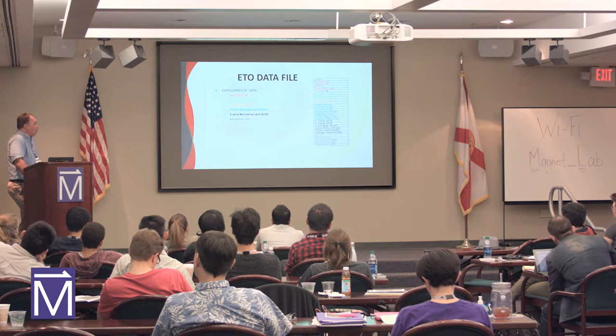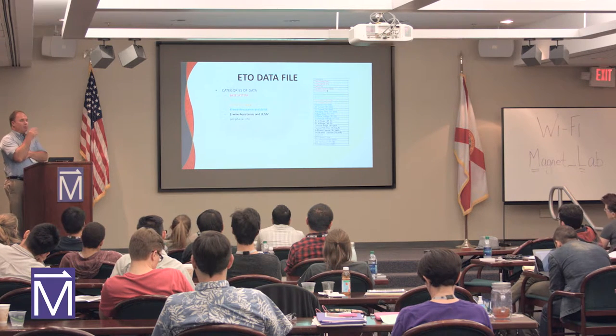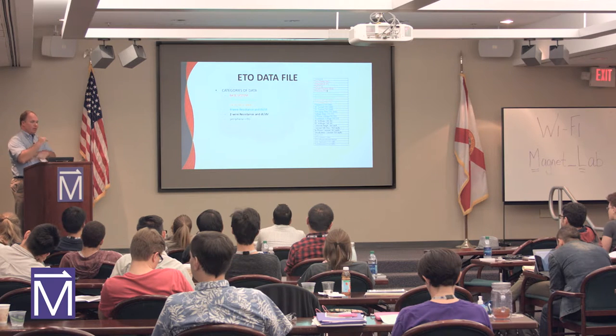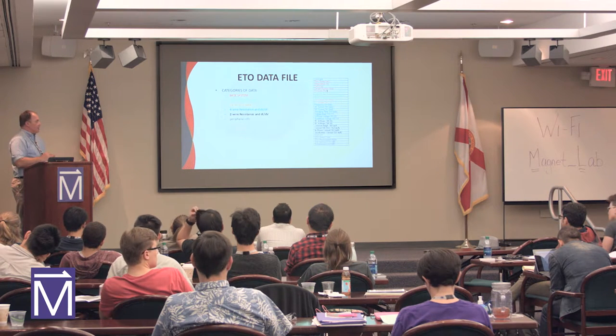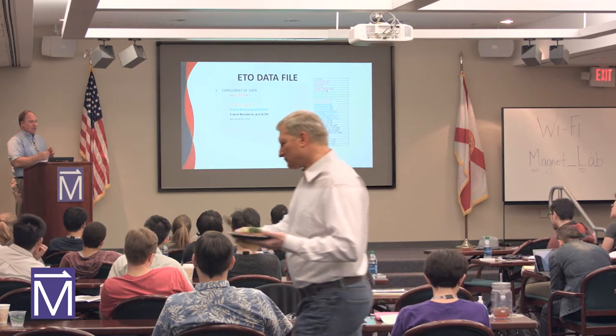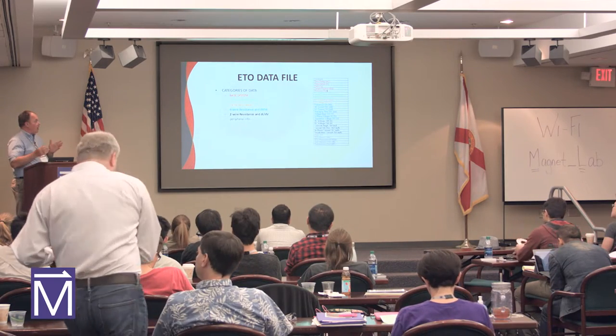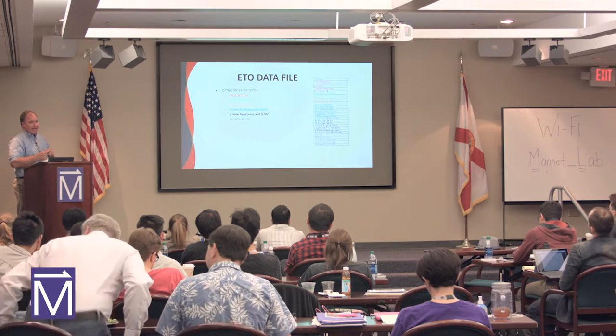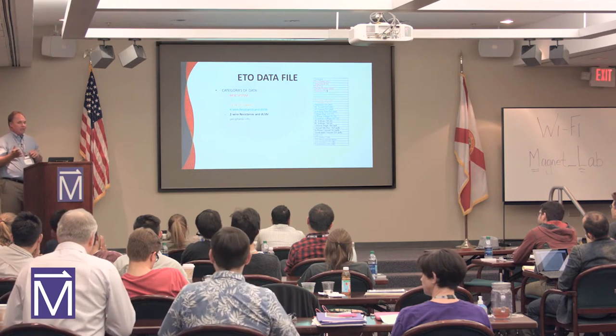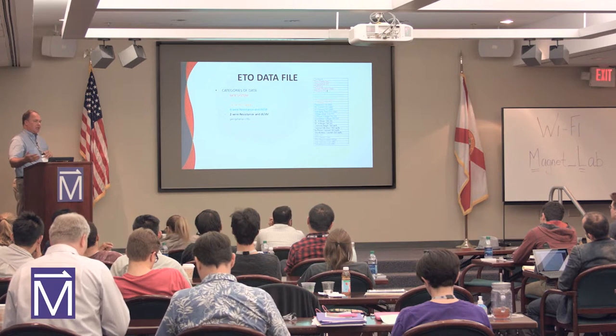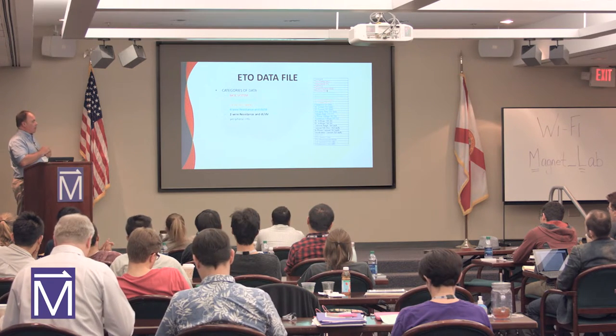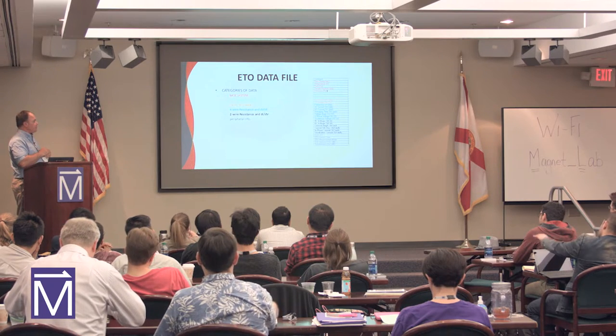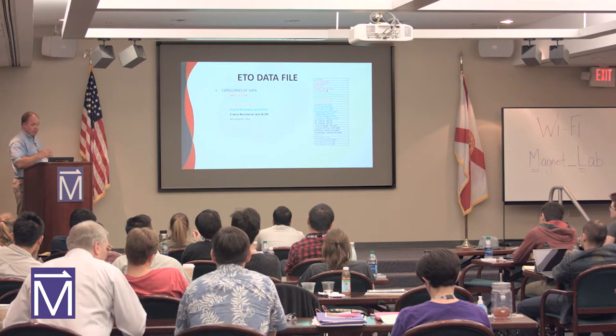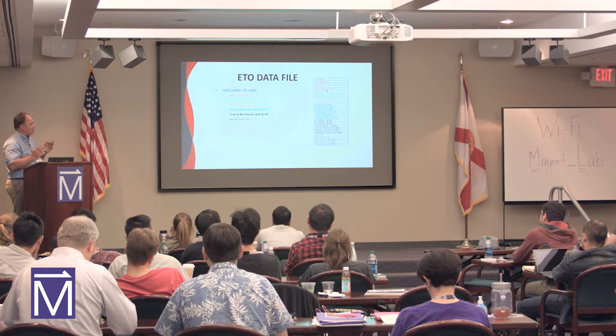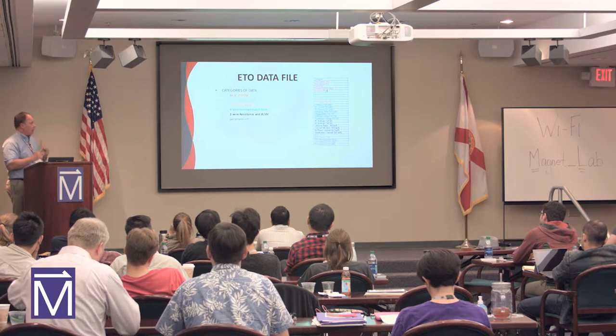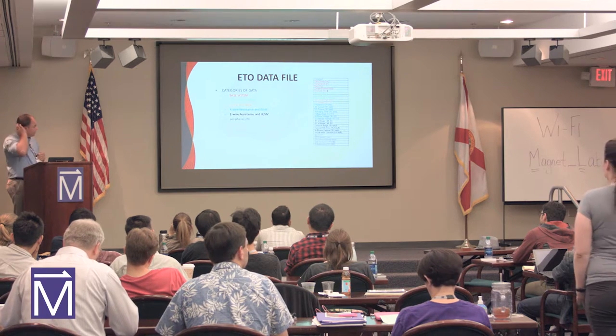In the data file itself, we report a lot of parameters in the system. So when we do the lab this afternoon, you'll see the data file from the VSM measurement. The ETO, the resistivity, all the other measurements have an extensive table of data. So you can see all the parameters of the entire system when you make a measurement. We'll talk in the tutorial about what we can look for in these measurements, but it tells you the type of measurement, the drive current, the voltages. So you can see all these parameters in the ETO data file.